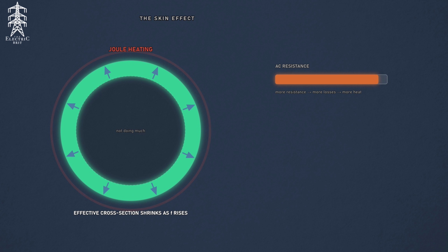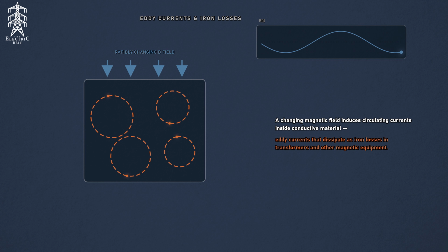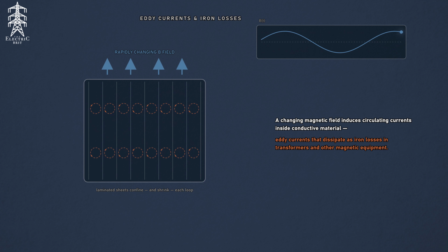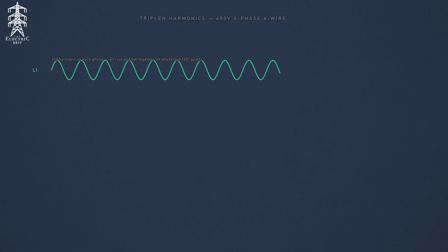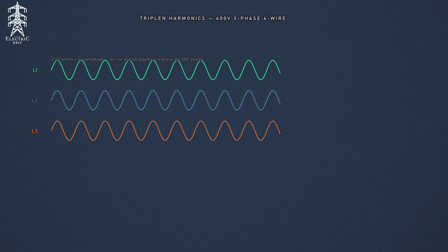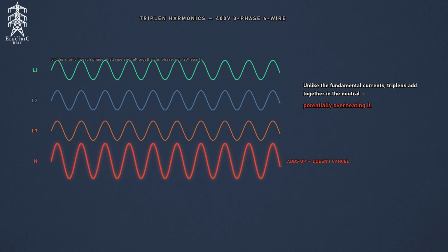increasing the resistance and causing it to heat up due to Joule heating. That rapidly changing magnetic field at higher frequencies is generating eddy currents, which contribute to the skin effect. And in transformers and other magnetic equipment, those higher frequencies also increase eddy current and other iron losses. Changing magnetic fields induce circulating currents inside conductive materials, and ultimately more of our electrical energy ends up as heat. And in three-phase 4-wire systems, like at 400 volts in the UK, triplen harmonics, like the third, are particularly troublesome, because unlike the fundamental currents, they can add together in neutral, potentially overheating it.